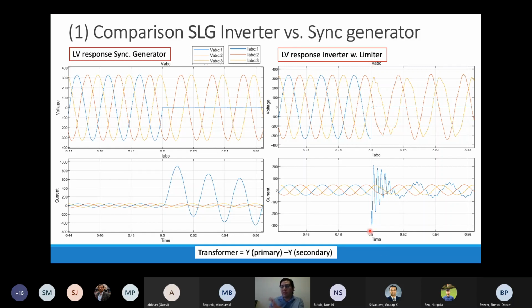So the figures might look the same, but if you pay a little bit of attention, we have the peak current, which is very high in the synchronous generator as expected, and any fault, as we know, this always happens. And on the right-hand side we have the inverter peak current, and we can see that in less than a cycle we are able to trim it and limit the current in order to prevent the inverter from damage. So the magnitude is totally different. This is a good point to address.